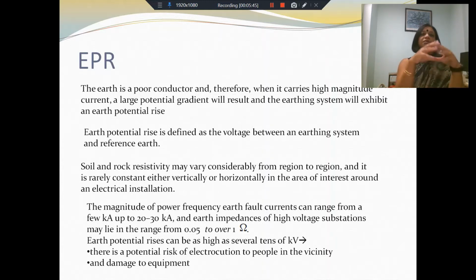And also, this is a variable, this is a quantity which varies from point to point. So you will not have, in any geographical region, a constant value of the resistivity at every point. There is a vertical variation, there is a horizontal variation. So at the point of electrical installation, there is a large region around it which will carry the high currents, and the resistance between any 2 points in this region can vary. As a result, you can have high potential rises.